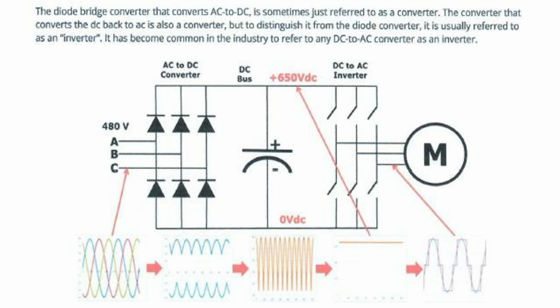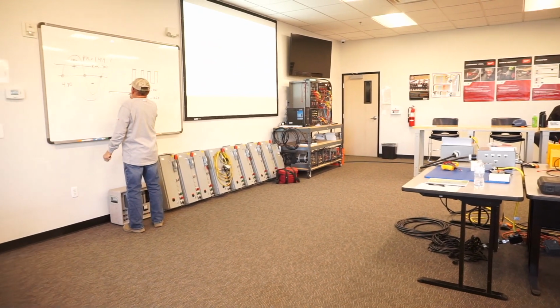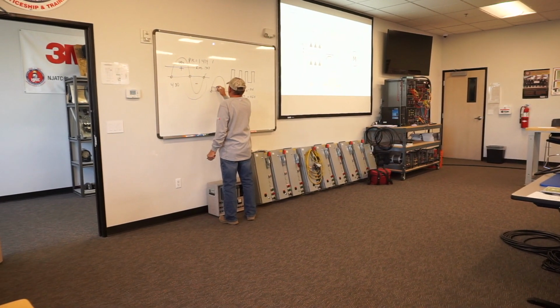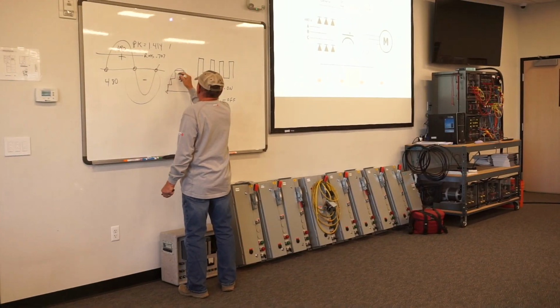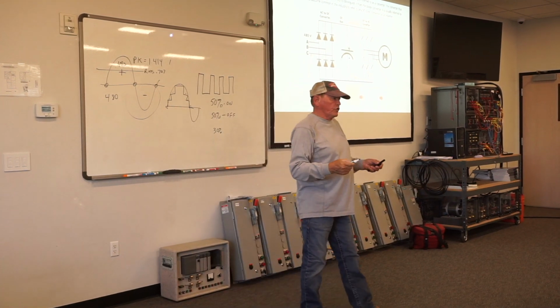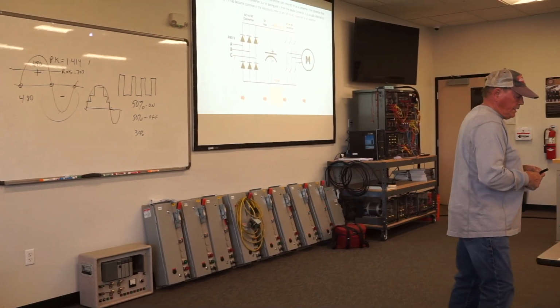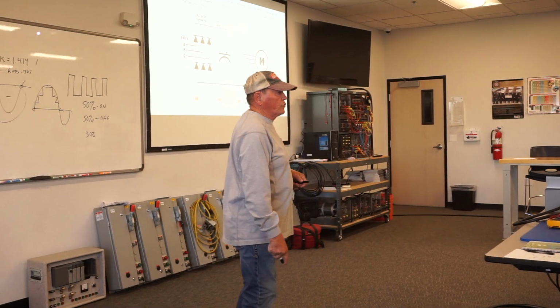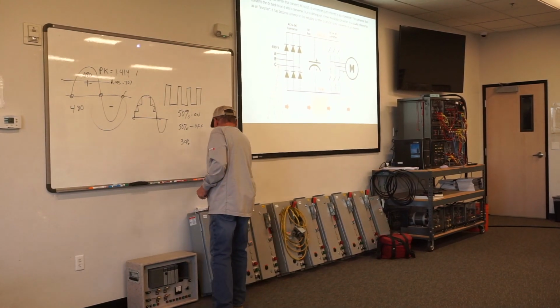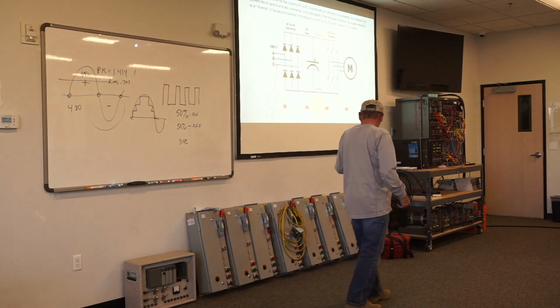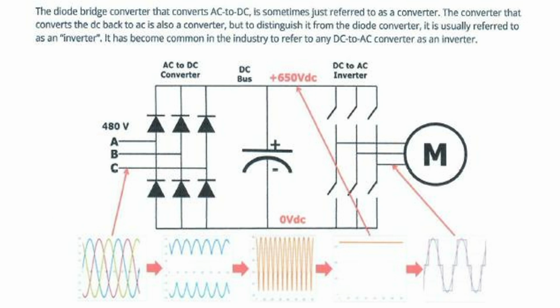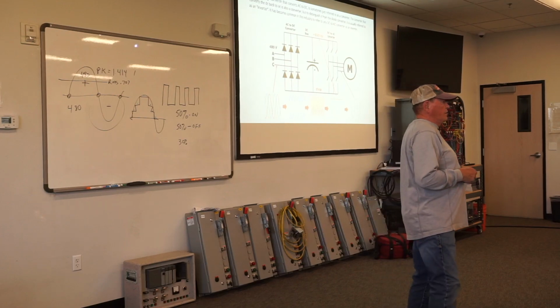And the inverter section starts putting out this 6-pulse signal, and it's going to actually have 6 steps to it. As it goes up, our sine wave goes up 3 times and down. 1, 2, 3, 1, 2, 3. 3 steps up, 3 steps down, 6 pulse. And that's what it looks like. And there's where the dirty power comes from, because it's not a smooth sinusoidal waveform. And that's what you're seeing here. Kind of hard to see, but there's 3 steps to the top and 3 steps to the bottom. Then we go to the negative side to develop the other half of the sine wave that the motor wants to see. So that's why bonding the motor becomes so critical.